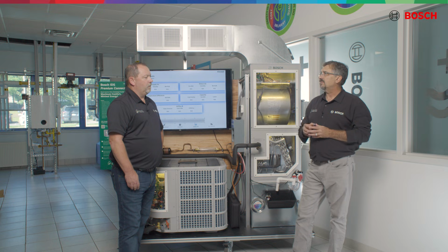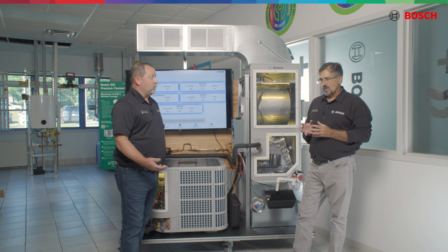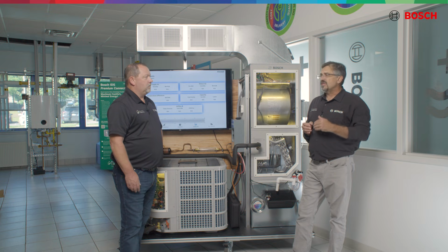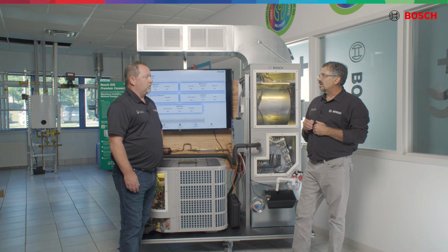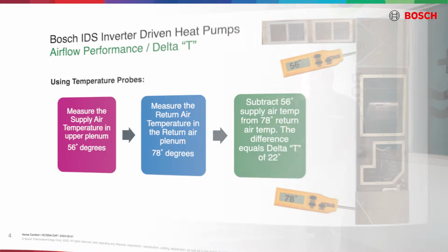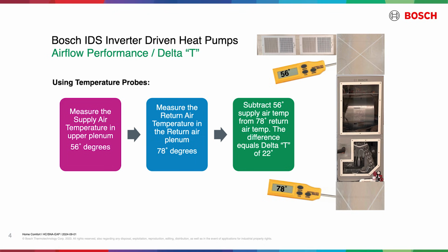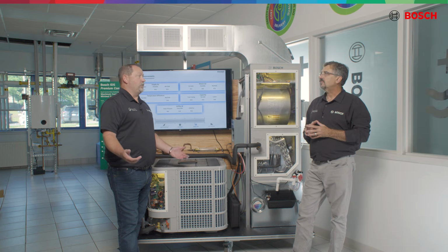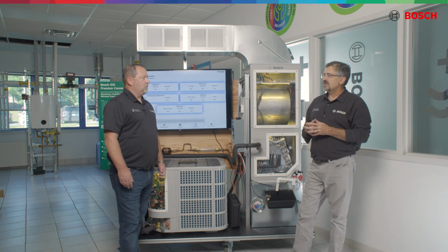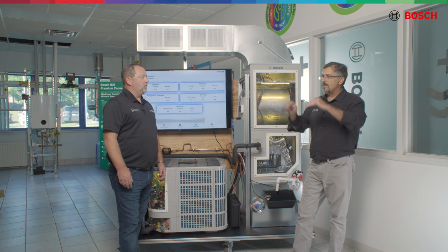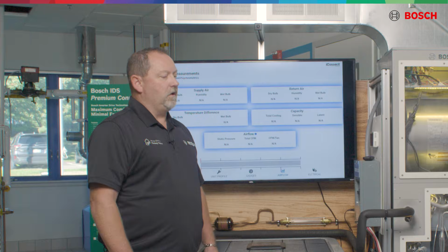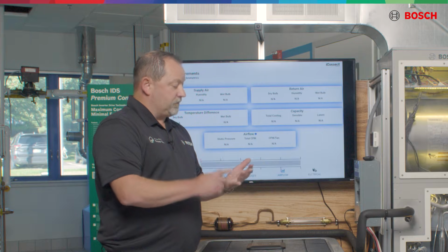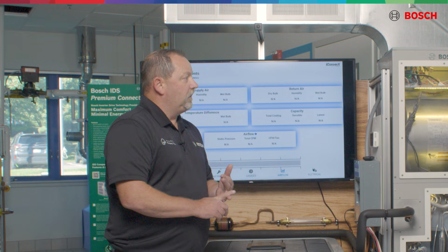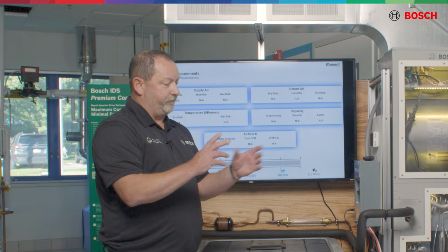Do we need supply air and return air temperature along with this calculation? We sure do. We need our delta T across that coil. That delta T across the coil is proving the air we're bringing in and the air we're delivering to the space. We're looking for that industry standard 15 to 20 degrees, but there's a lot of variables that come into it. It could be as high as 22 or 25, I suppose. It could be. This Bosch system actually could run as high as 30 in the right conditions, and then back down as that coil gets colder. Okay, so we need supply and return air temperature for our calculation.